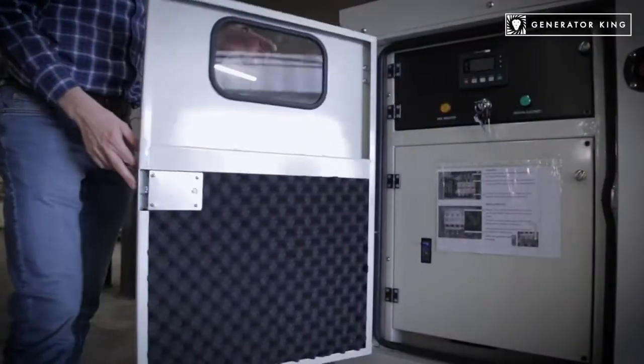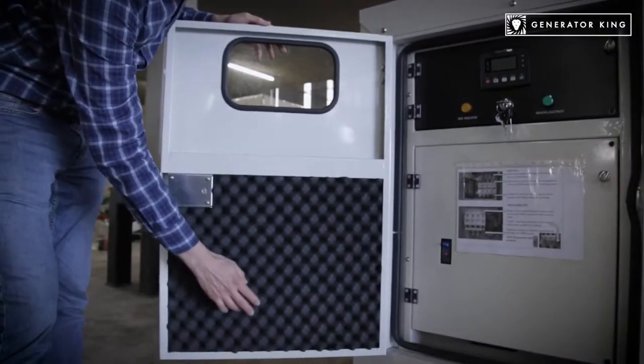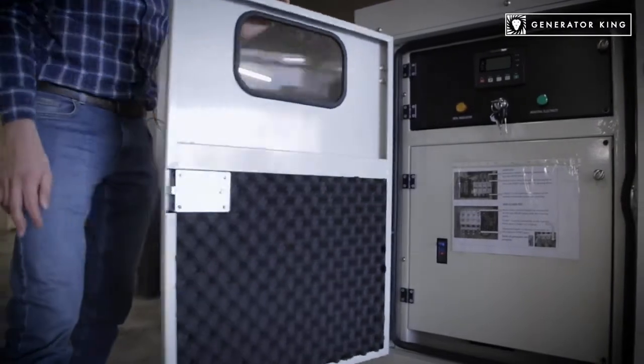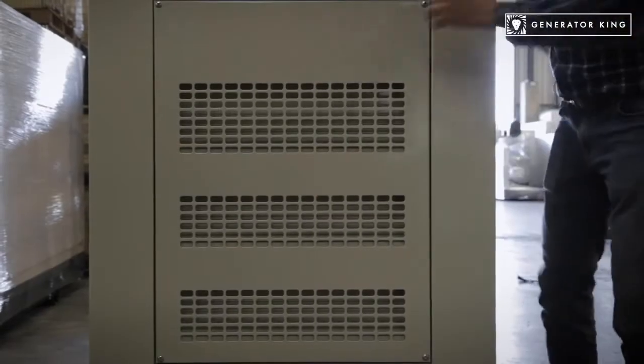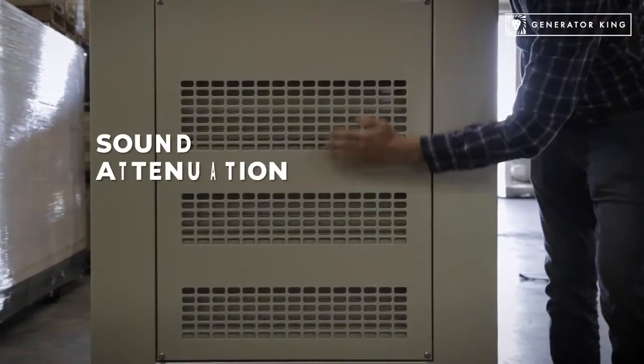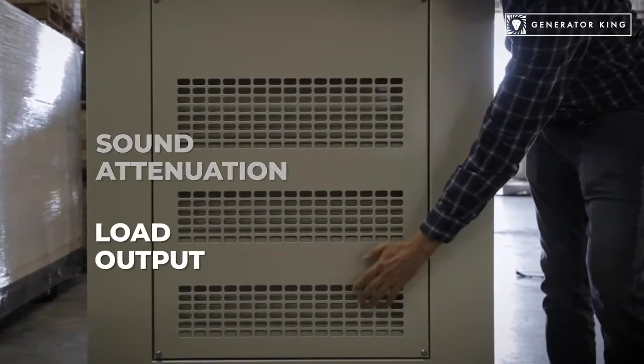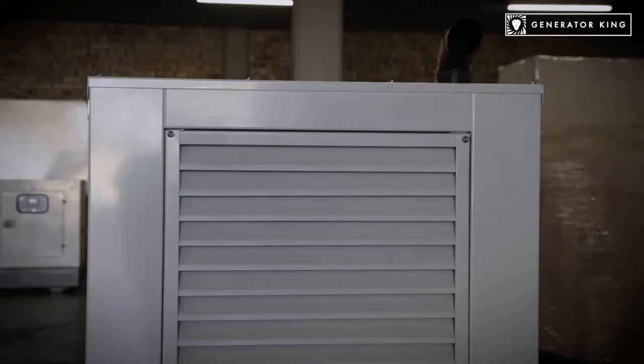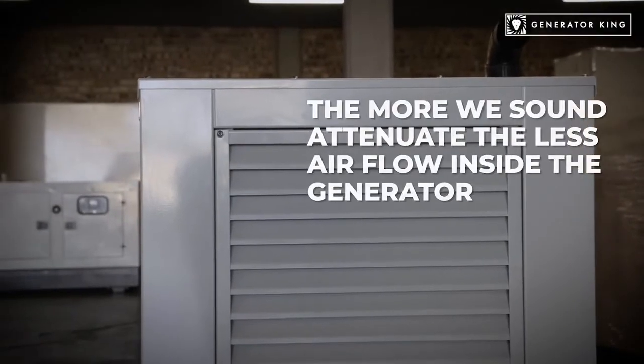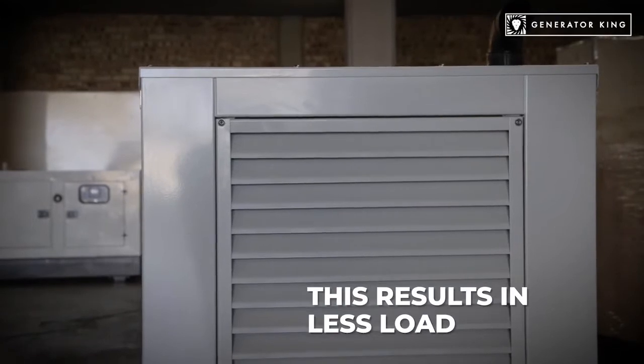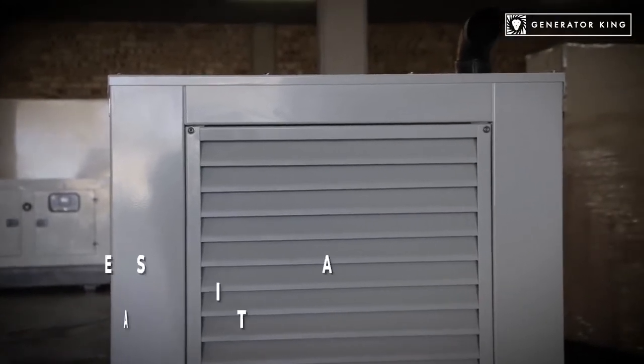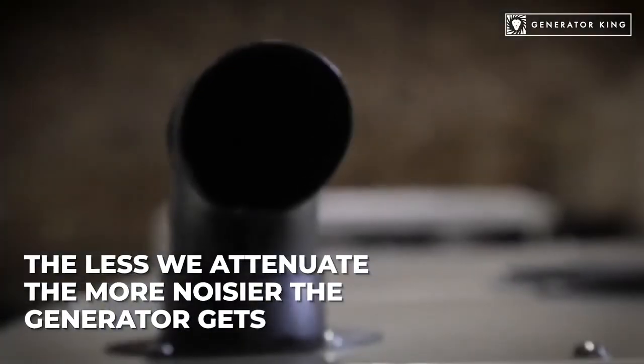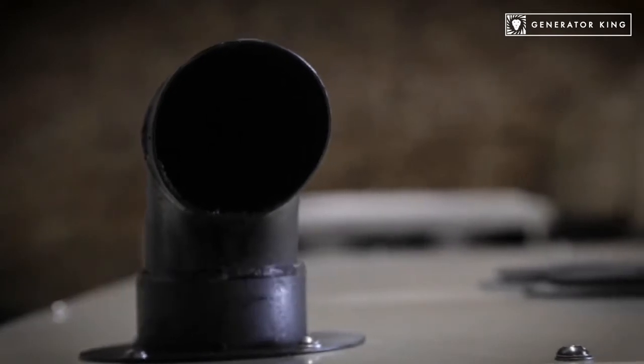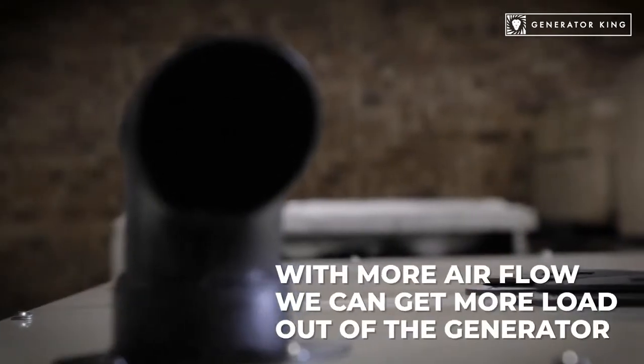Let's talk about the key features to consider about sound attenuation when purchasing a diesel generator. There is a fine balance when we build a generator between sound attenuation and load output. The more we sound attenuate it, the less airflow there is inside the unit and the less load you can get out of it. The less we sound attenuate it, the more noise it gets, but we can have more airflow so we can get more load out of it.